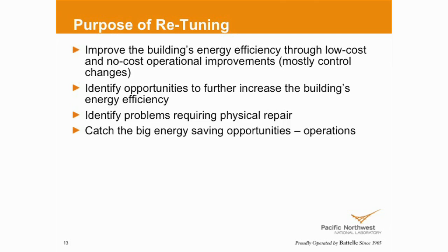So we have some definitions. Retro-commissioning, recommissioning, continuous commissioning. We've already talked about some of that. Retuning, our definition of retuning is that it's a no or low cost method to save energy. And the methodology is focused on low and no cost operational improvements. So we're primarily talking about your operational staff, your O&M staff. Again, it's pretty much related to setting up your control systems to some known design, configuration, set points, schedules, and algorithms if they need to be added to achieve hopefully a better building.